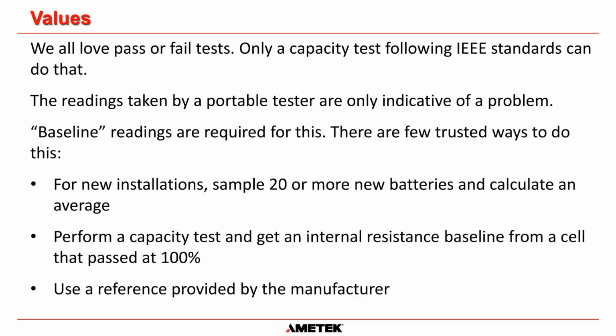So the few trusted ways to get a baseline, the best way is when you newly install the battery. They're saying that you should sample 20 or more of the new batteries and calculate an average of the baseline readings for that. Now, it's extremely important when you install that battery that you're thinking ahead and you know which portable tester is going to be tested and used on that battery over its life.